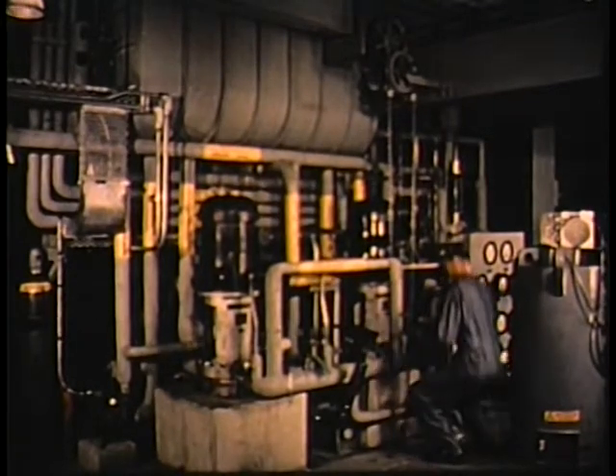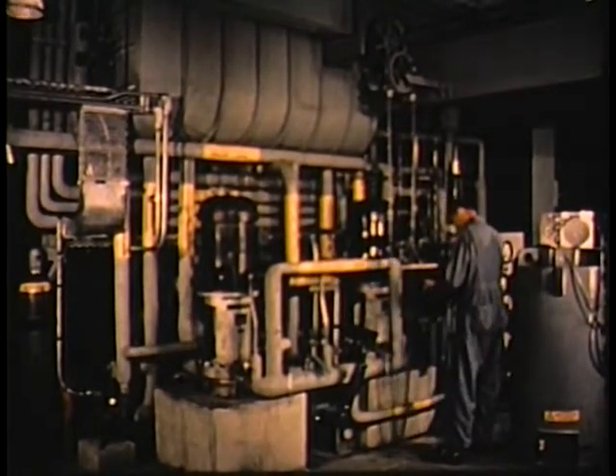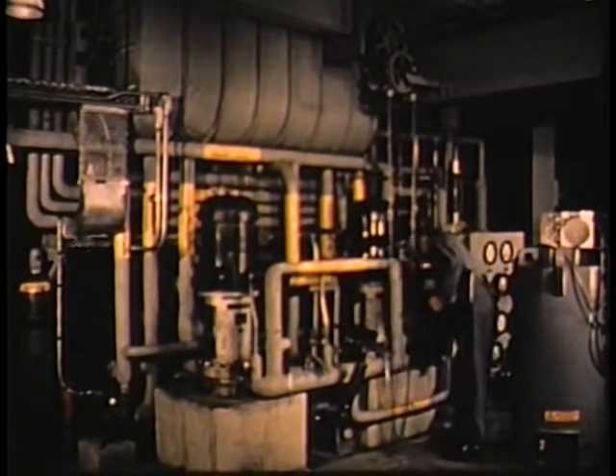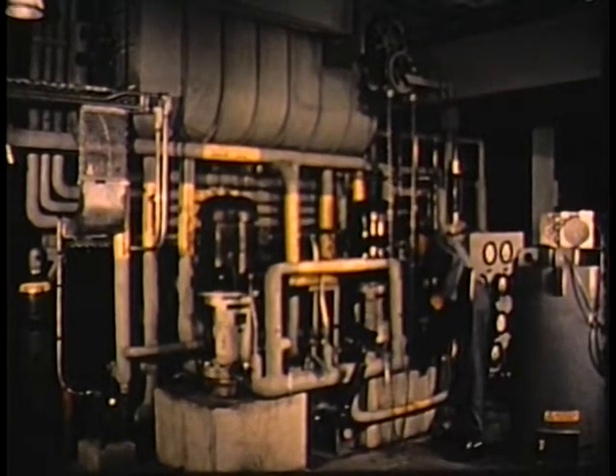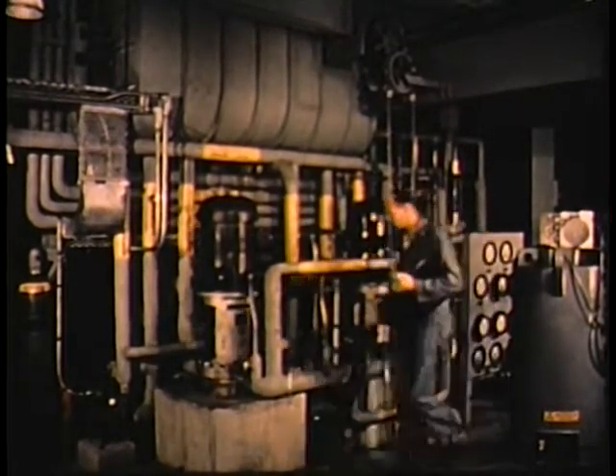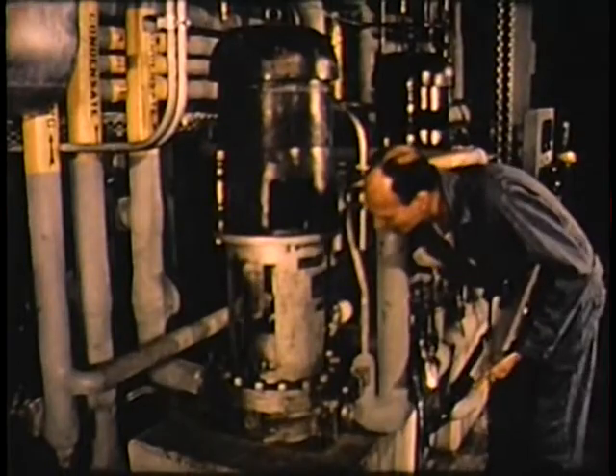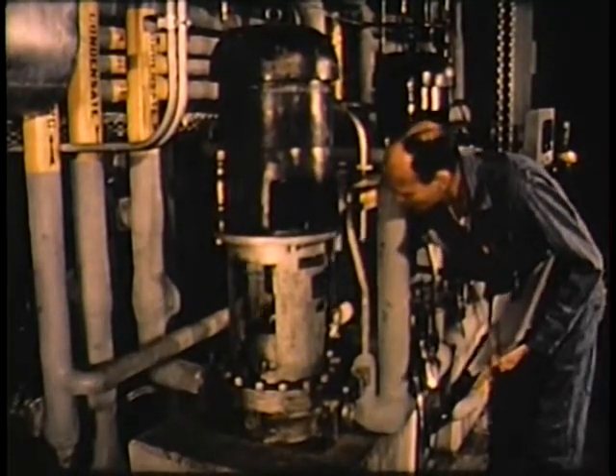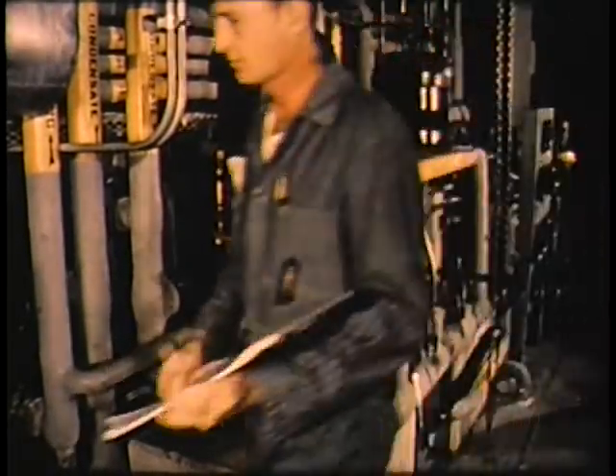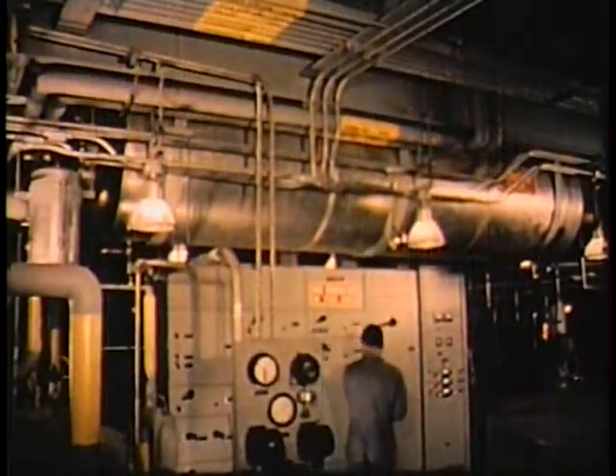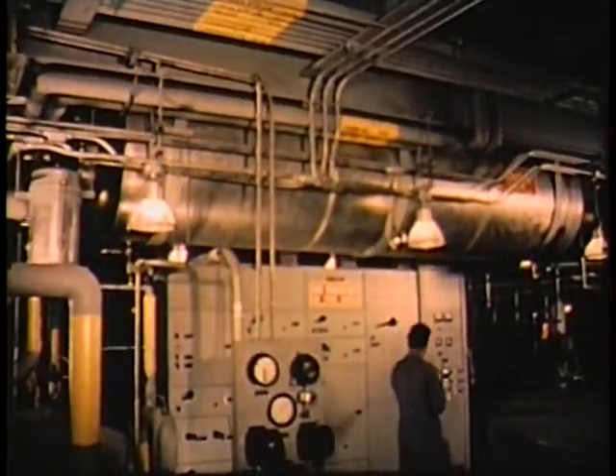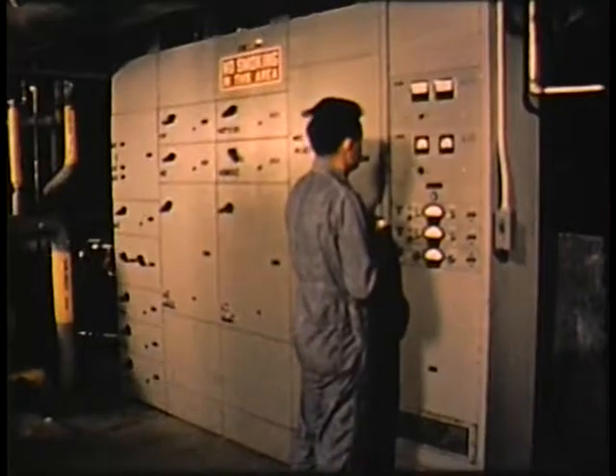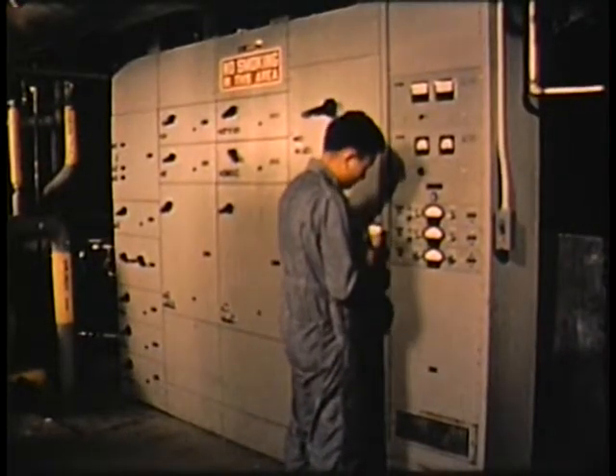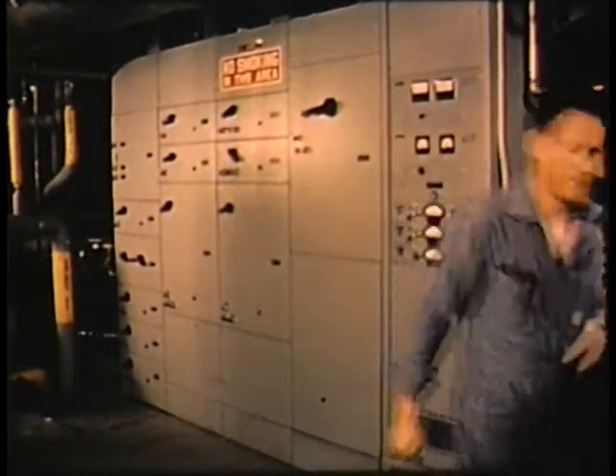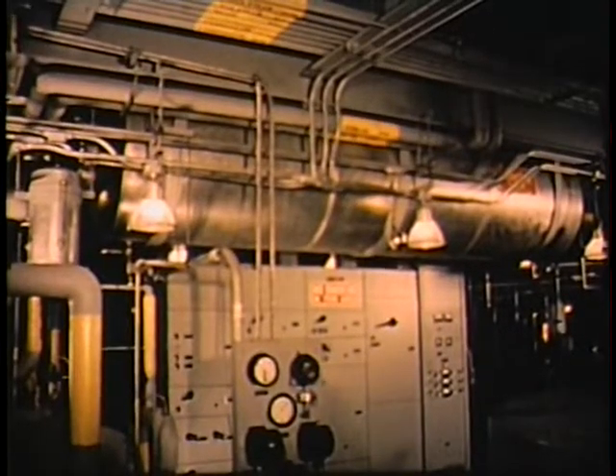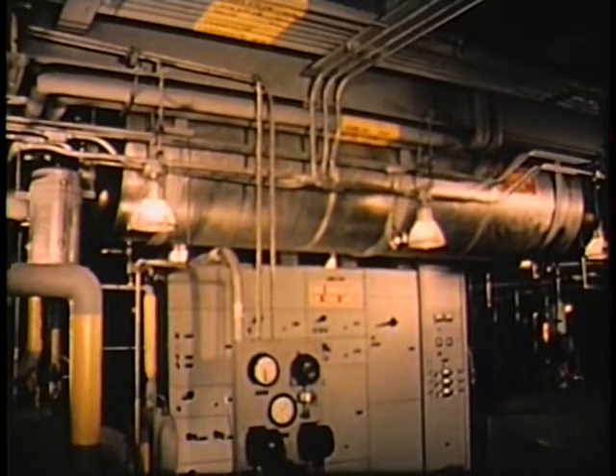In the event of the failure of one feedwater pump, a second pump is started automatically to carry the full burden. Feedwater flow is regulated by a three-element control system that correlates measurements of the mass flow rate of steam from the vessel, the feedwater return rate to the vessel, and the reactor water level. Under equilibrium conditions, water level is held constant at a preset point, and feedwater flow matches mass steam flow.